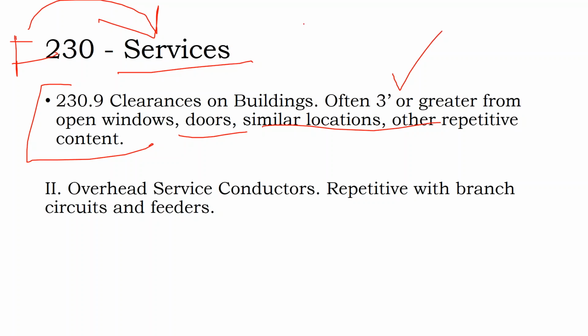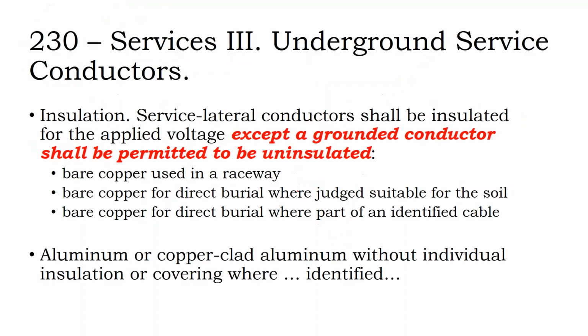I think they look a lot better, and I think those aesthetic values are very important. But a lot of installers will just stick to the outside of the building for a variety of reasons. When you're running that conduit down the side of a building, you have to stay 3 feet away from windows and doors and, you know, the ability for a human to open up a window and stick their arm out, wave at the parade that's going by the window. You don't want them to get in contact with that line.